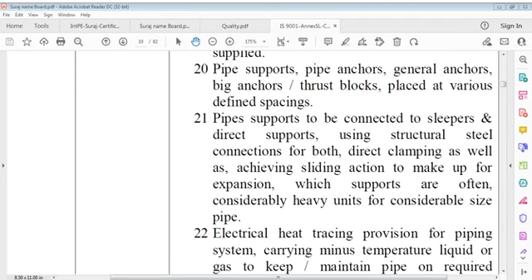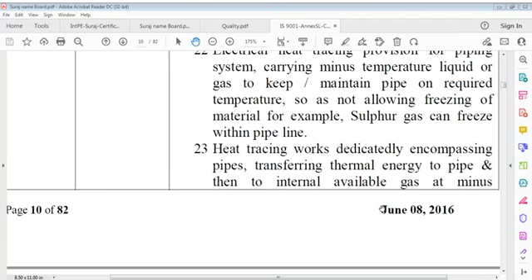Electrical heat tracing provision for piping systems carrying minus temperature liquid or gas to keep and maintain pipe at required temperature, so it's not allowing freezing of the material. For example, sulfur gas can freeze within pipeline.